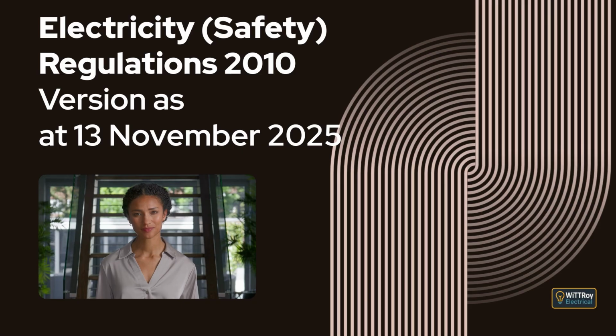Reg 81, Evidence of compliance with standards. This regulation explains that a test report or certificate of conformity showing that a low voltage or extra low voltage fitting or appliance complies with AS/NZS 3820, or with a standard listed in Schedule 4, is conclusive evidence of compliance unless proven otherwise. It explains that a test report must be an original or certified copy issued by an appropriately accredited or approved laboratory, or under the IECEE CB scheme. It also explains that a certificate of conformity must be issued by a recognized and accredited certification body, either under the Joint Australia and New Zealand accreditation system or under an international mutual recognition arrangement.